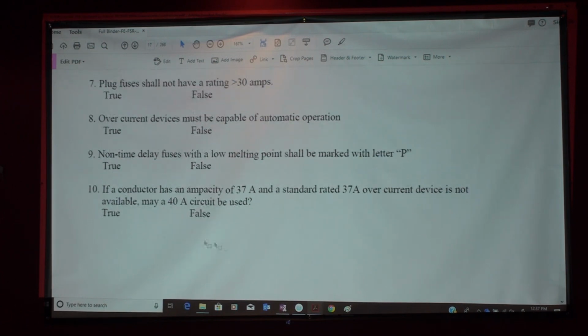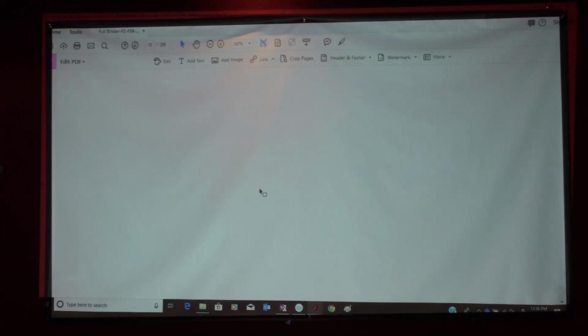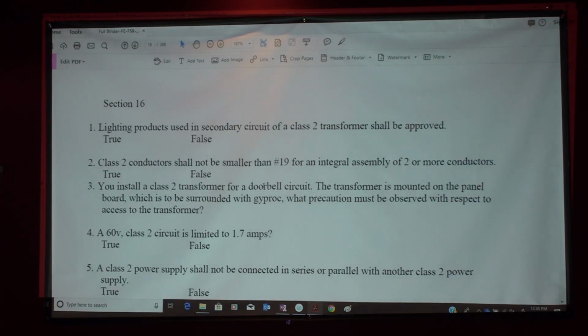We highlighted this. If a conductor has an ampacity of 37 amps and the standard rated 37 amp overcurrent device is not available, can I use 40? Guys? Yes. Awesome. If your conductor is 37, you can't choose a 35 amp breaker or it will trip right away. So you've got to use equal or higher. Okay? Alright, we keep going. Section 16, first person after that. Lighting products used in secondary circuit of a class 2 transformer shall be approved. True or false? True. Good job.